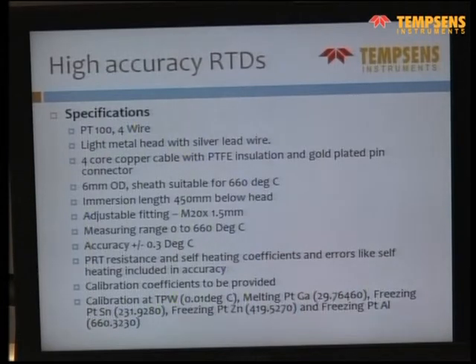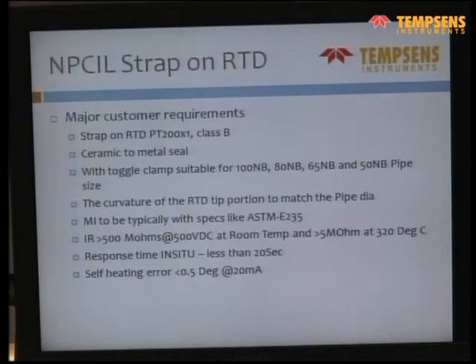These are special RTDs which we have to offer with 0.3 degrees accuracy over a measuring range of 0 to 660 degrees centigrade. This can only be done by having a special curve for each RTD. Each RTD was checked at 5 fixed points, and a special curve was offered to the customer so that he can get it in this accuracy range. And there was a special arrangement made so that the drift is minimum for these RTDs.